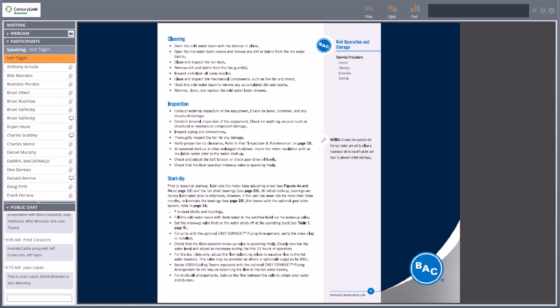You want to check the general condition of the equipment. As I mentioned before, you want to check the fan for any damage. You want to verify that the fan is spinning properly, that the fan cowl is not impeding on the rotation. And again, you want to check the gear oil levels. You want to adjust the belt tension. And then check to make sure your float is operating properly.